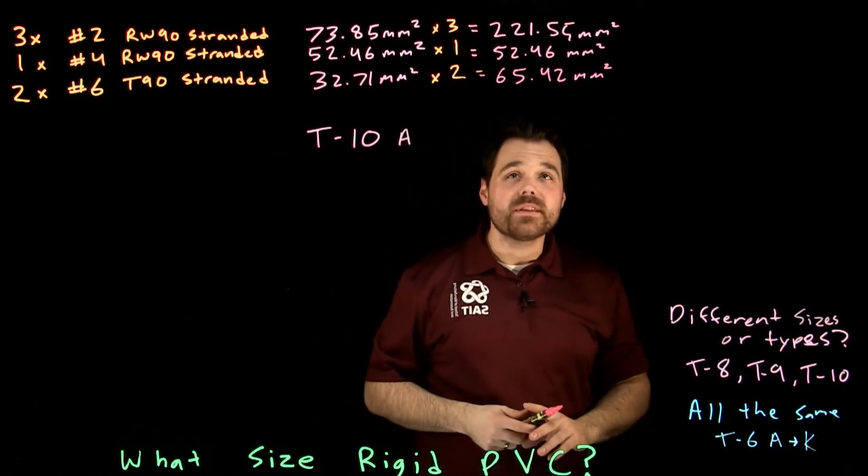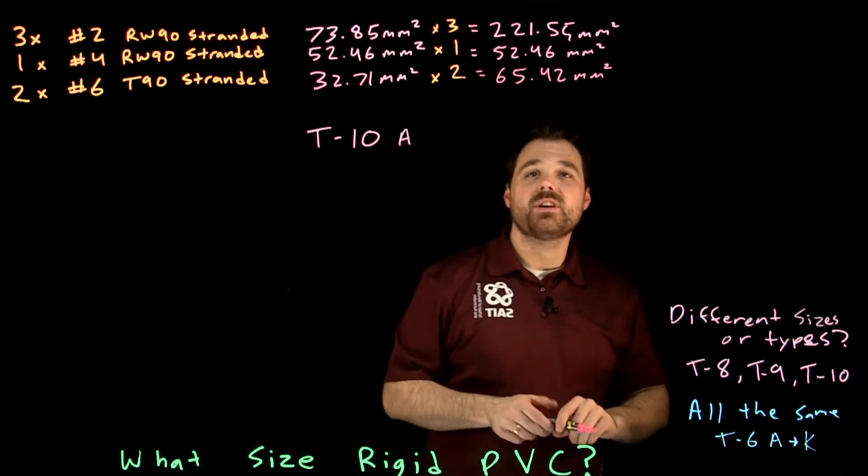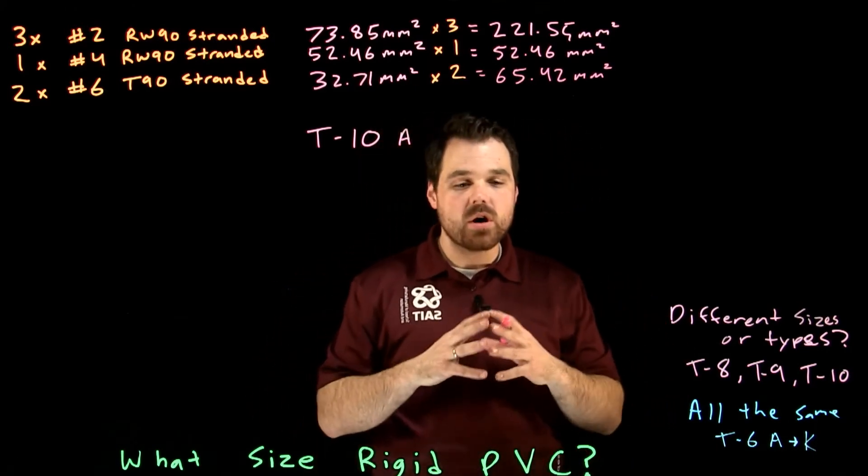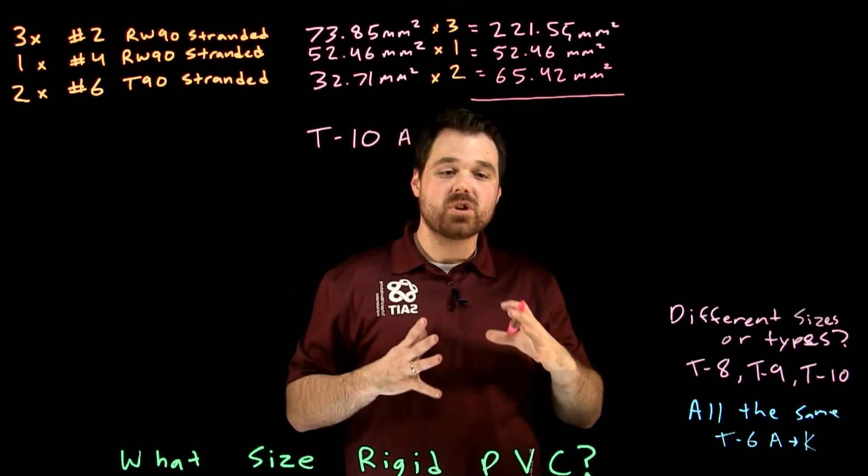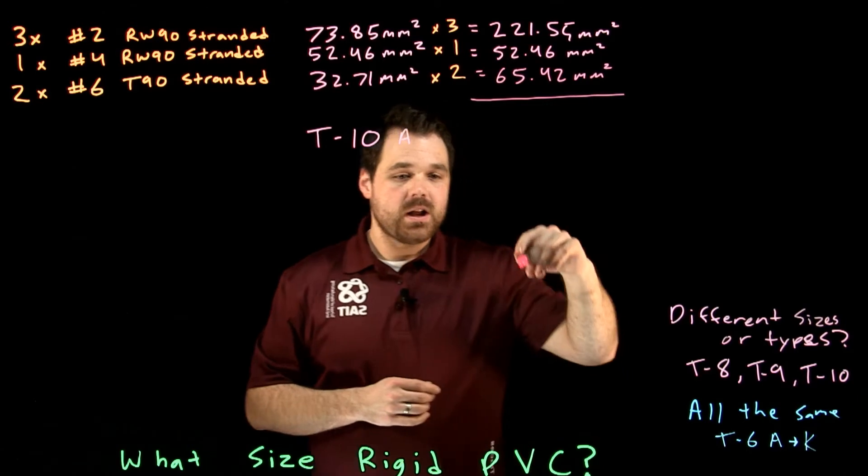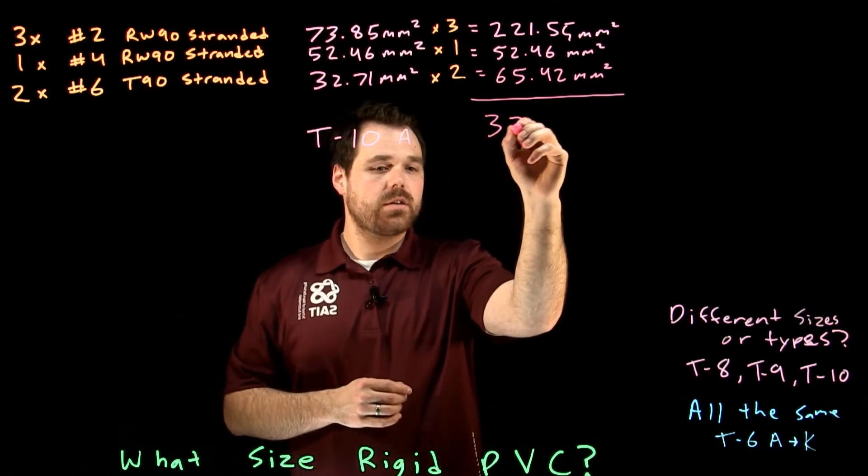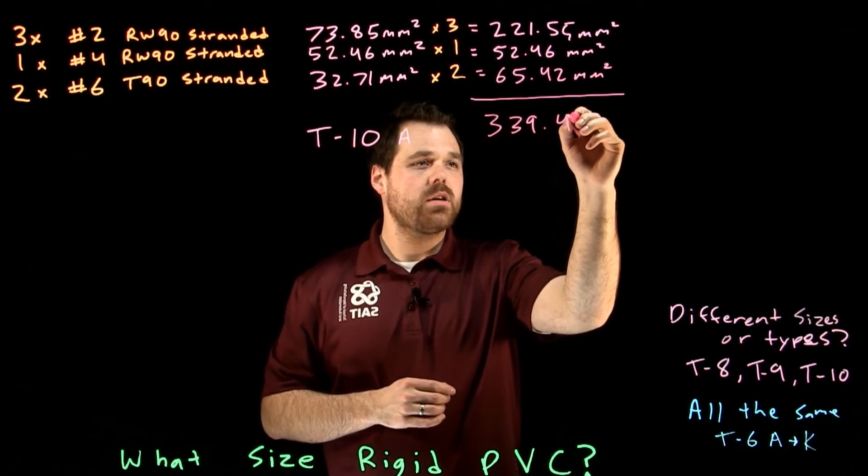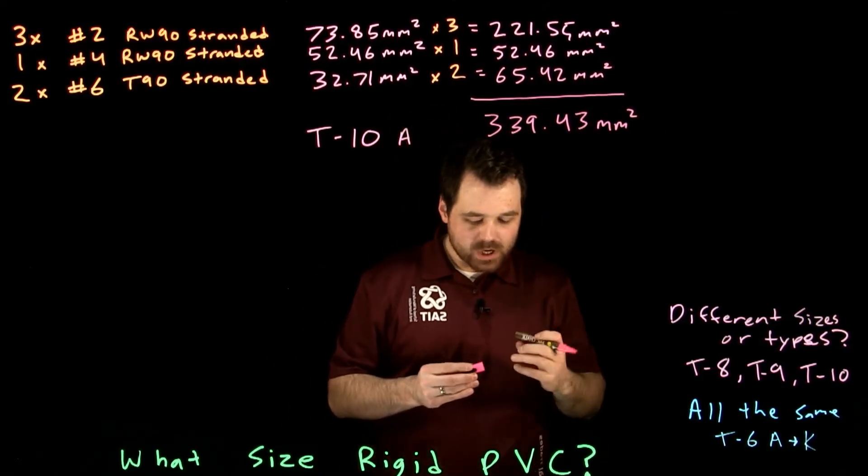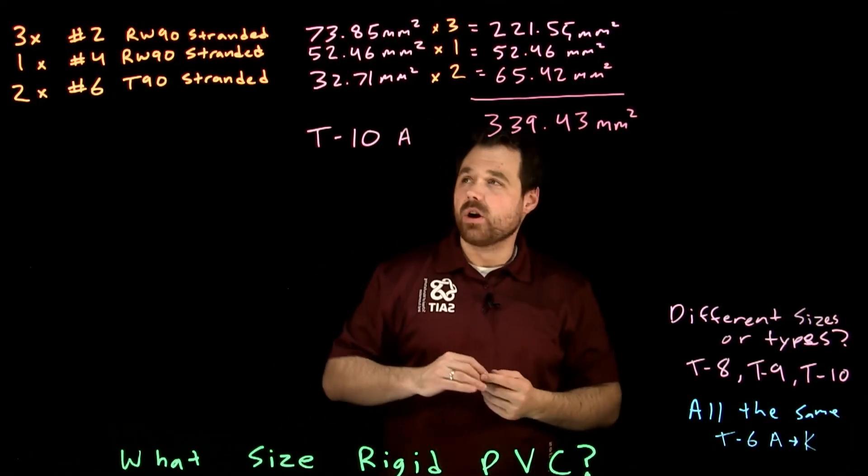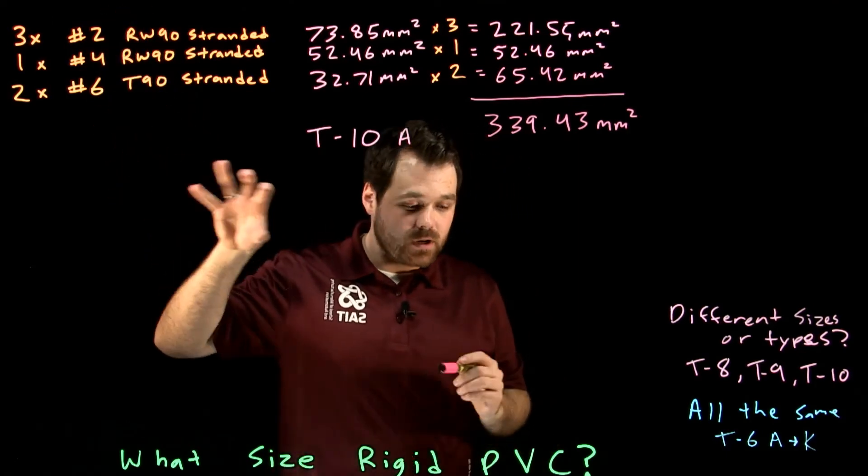So what we do with this info is we have to get a total. The area which all of those conductors are going to take up inside that conduit. So we add all these up and we get the total area that we require is three thirty nine point four three millimeters squared. So that's how much space that all of these conductors, when pulled in a conduit, are going to take up.